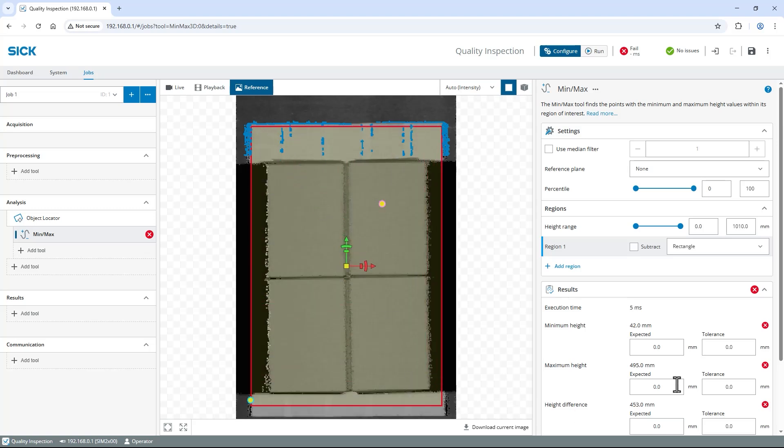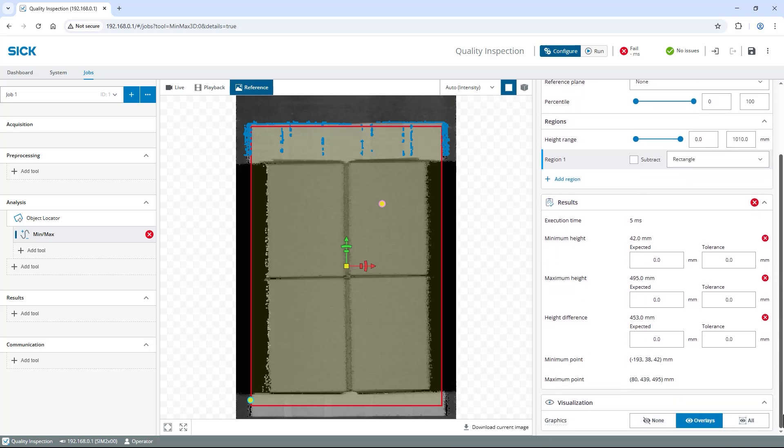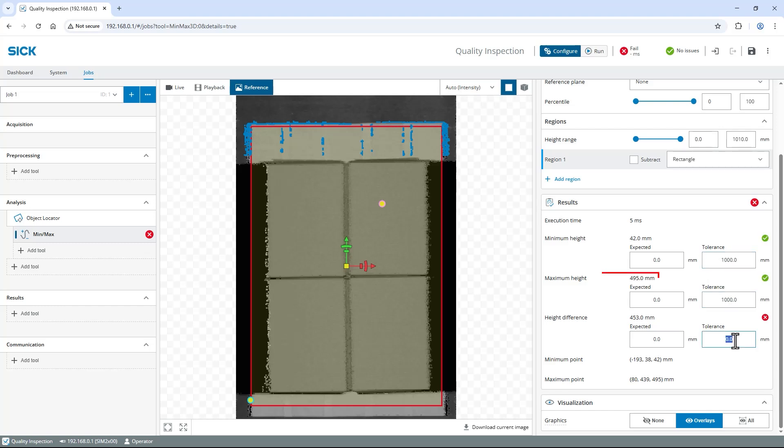Scroll down to the Results section to see the measured values. For my height measurement task, the maximum height value is perfect. Here, you could set expected values with tolerances for your pallet height to get a pass or fail result. To always get a pass result of the tool, I set the tolerances to 1000 mm and just use the actual maximum height value further.